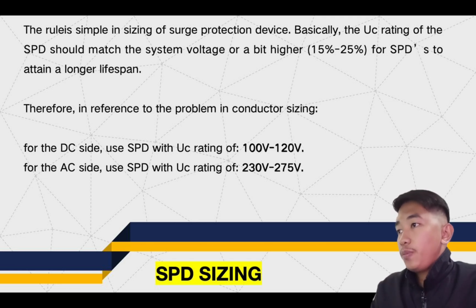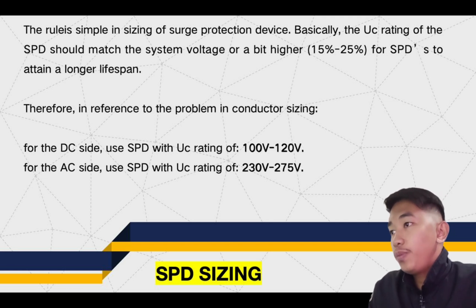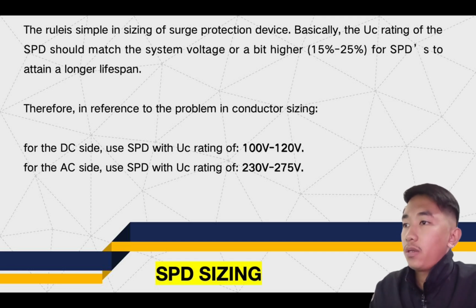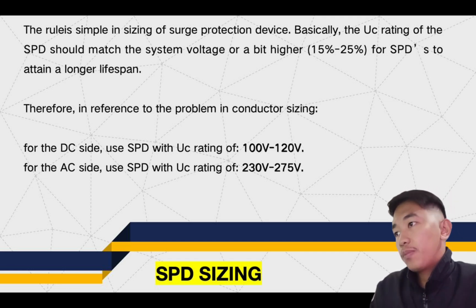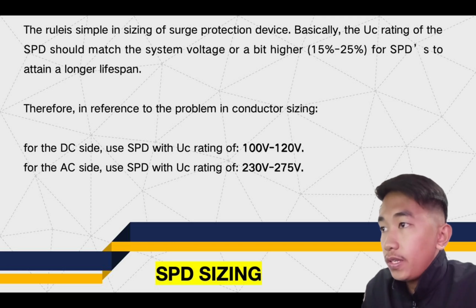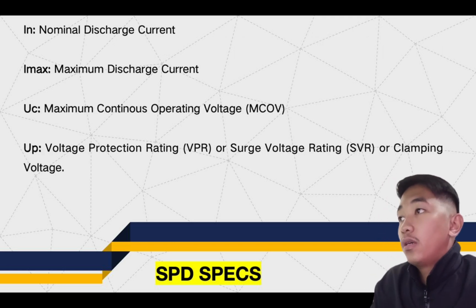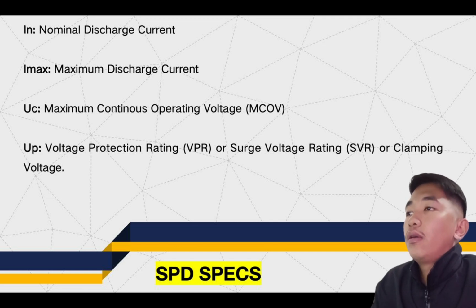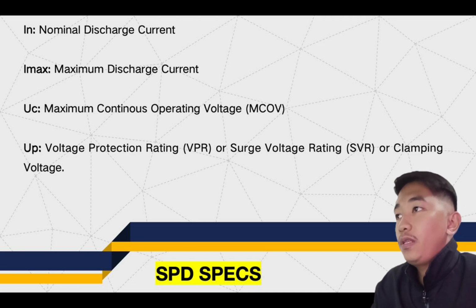So sabi lang dito sa SPD na para mas mapahaba natin ang lifespan ng ating SPD, it should be a little higher than the system voltage. Once again, dapat mas malaki lang ng bahagya yung UC rating dun sa system voltage. Nominal discharge current, or I sub n, in the context of surge protection devices, refers to the peak value of surge current with an 8/20 waveform that the SPD can withstand for 15 surges without failing.